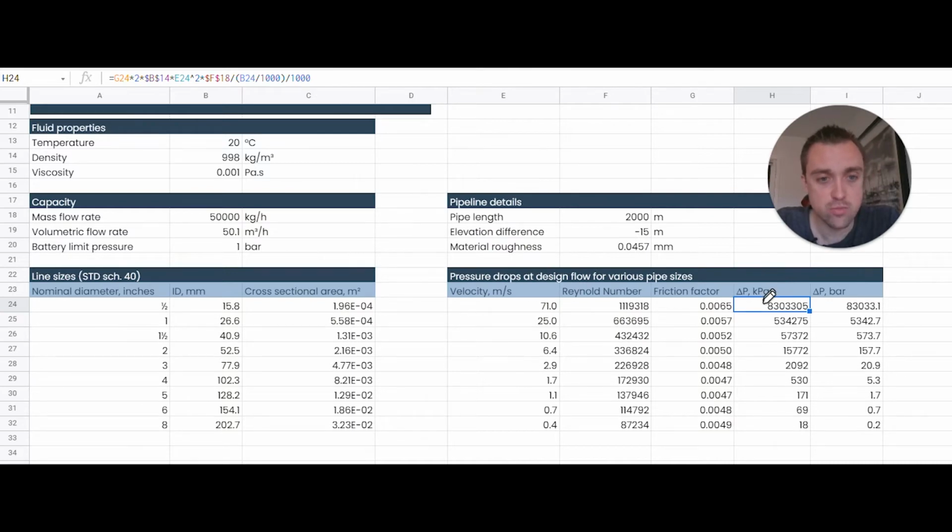And here I've got the pressure drops in kPa, and I've converted them over to bar because I'm most comfortable working in bar. You can see if we started with this half-inch tube, we would have 83,000 bar worth of pressure drop. That's not going to happen. We're not using a half-inch tube, right? It is simply too narrow to pump through feasibly.